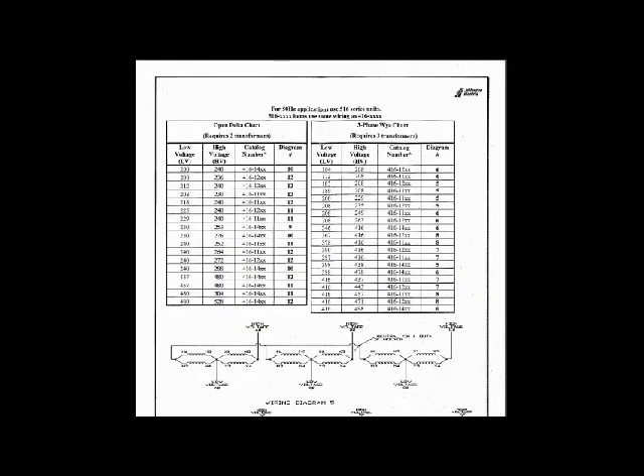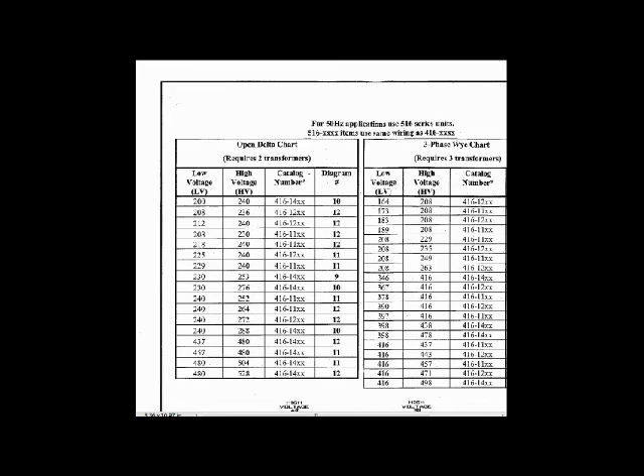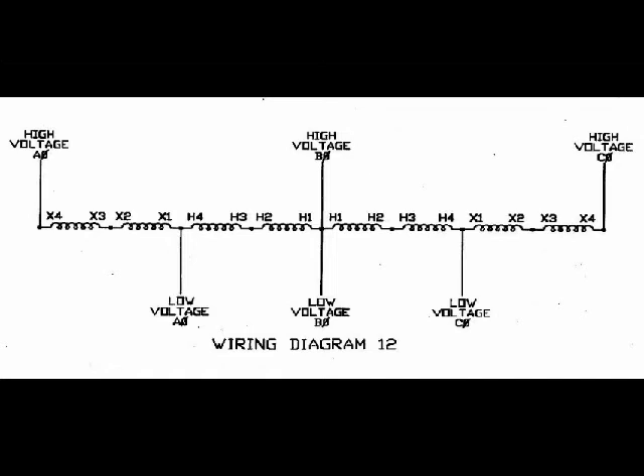Because it's three-phase, we're going to need more than one. This particular transformer allows us to step up from 208 to 230 in either an open delta configuration or a three-phase Y configuration. The difference is with a three-phase, we would need 3 transformers, and with open delta, we would only need 2. So being the pinch pennies that we are, we'll do open delta and go to this 208 boosted up to 230 volts. So that's going to take us to diagram 12 in this information that came with the transformer. And here it shows us where our high voltage connections are made and where our low voltage connections are made.